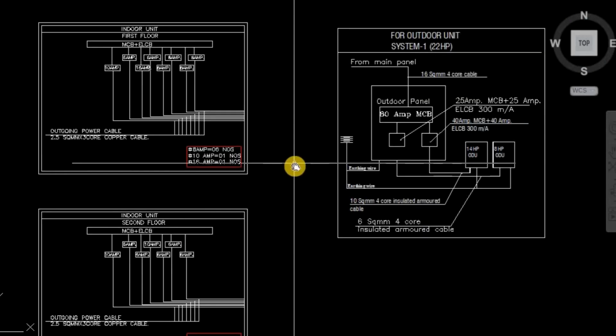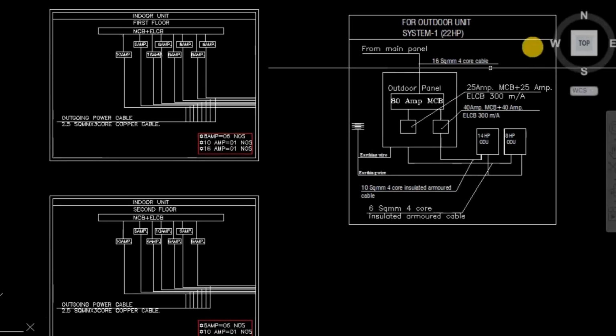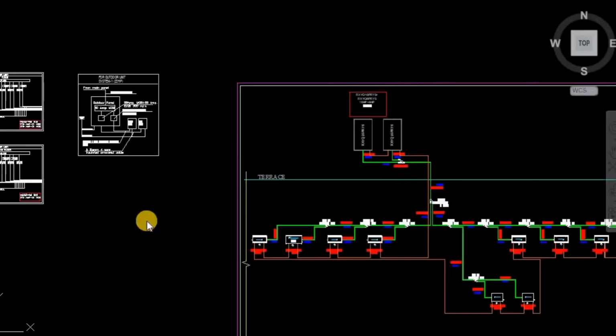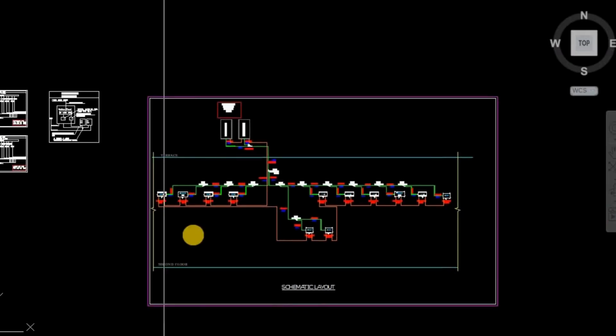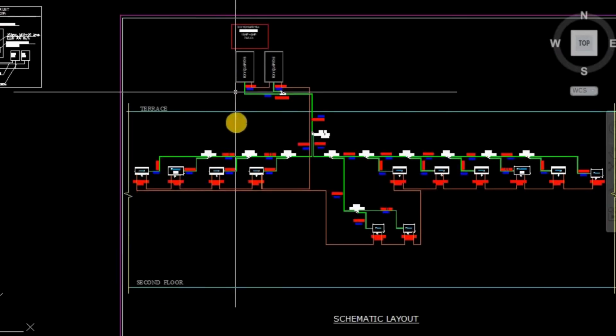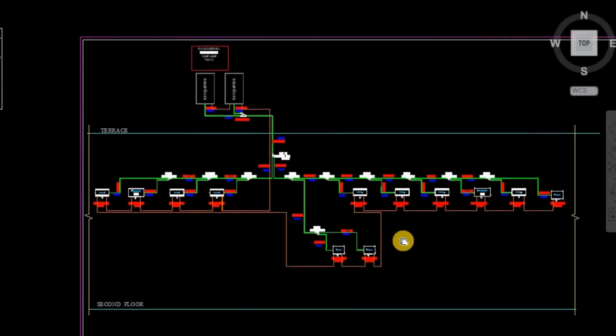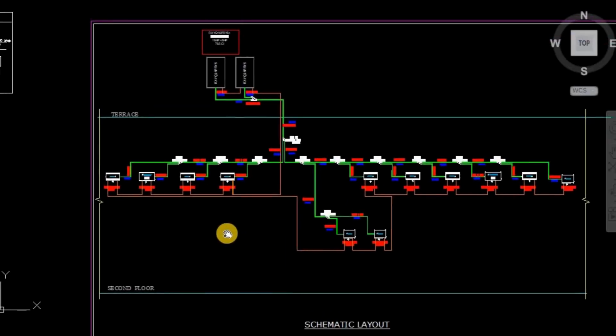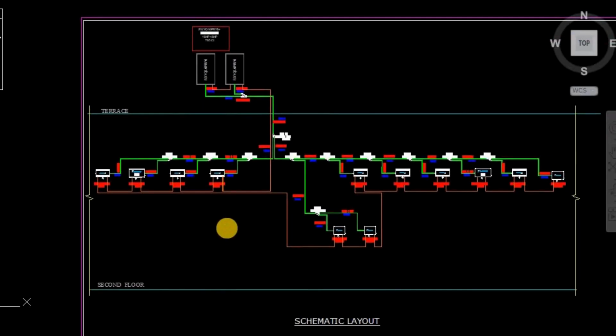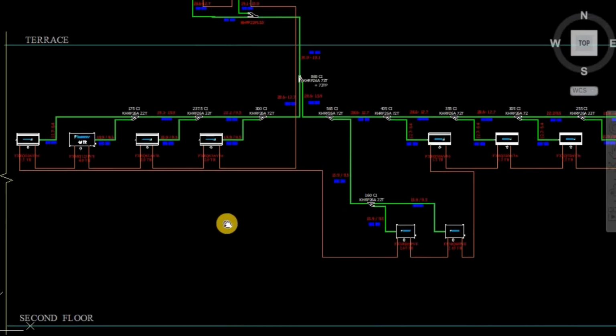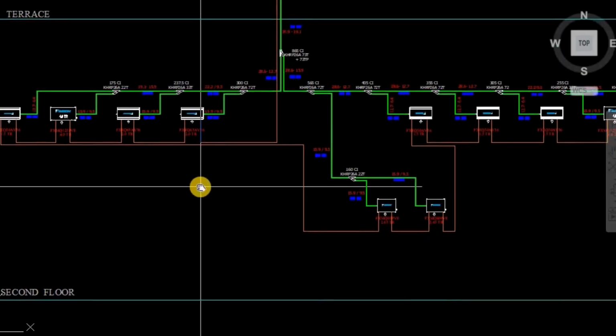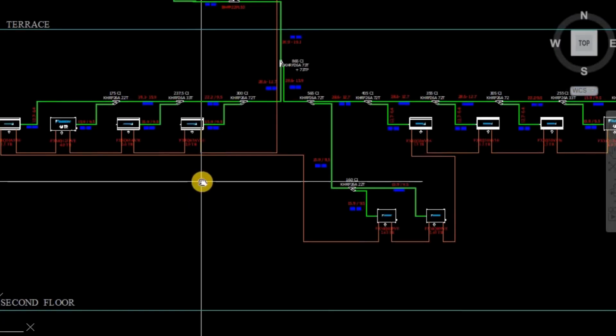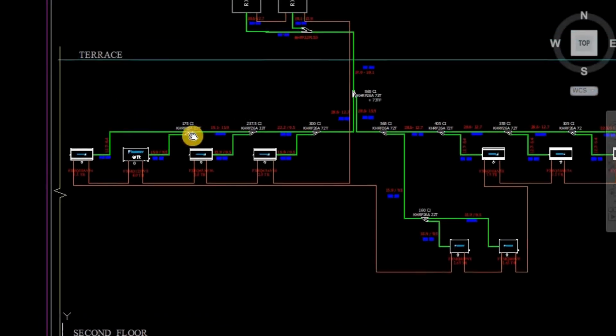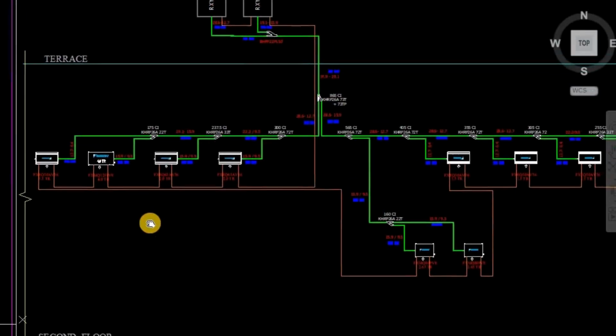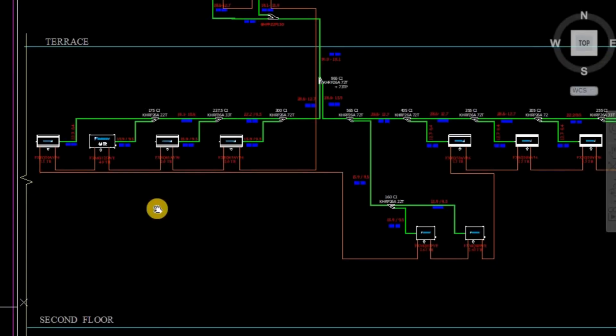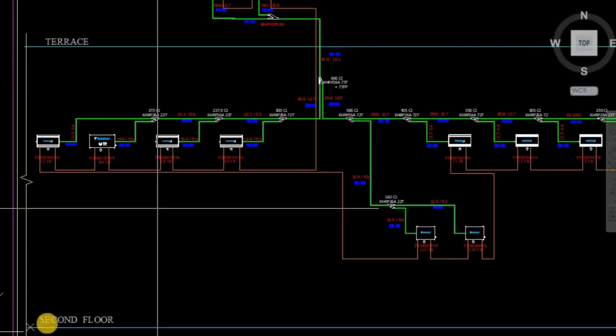Friends, always use the Daikin specification as per requirement. See the Daikin manual for any doubt. And next comes the control wiring. The control wiring connects the outdoor unit to the indoor unit, and to the centralized control system if there is one. The Daikin VRV typically uses 2-core 1 square mm cable for communication and data transmission. Maintain the correct polarity, cable type and distance limit as recommended in the installation manual. Okay friends, always avoid running power and control cable together in the same conduit to prevent interference. Always tighten the terminal screws properly to prevent loose connections.